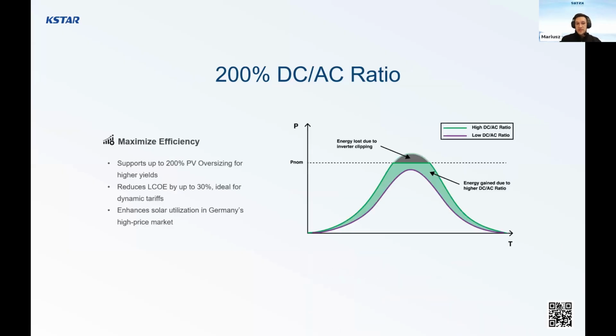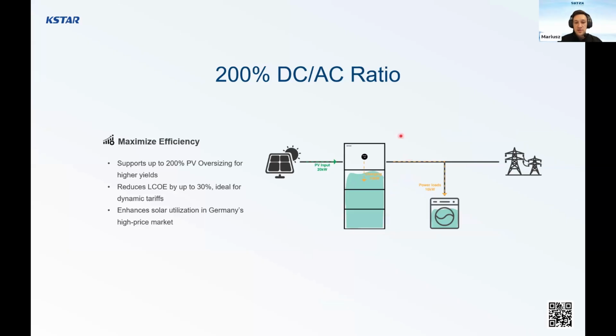Regarding the 200% DC-AC ratio, that's what I mentioned about. We have two converters. So, for example, if we connect to standard PV string inverters or other brand hybrid inverters, the power can be cut at the maximum nominal level of the inverter. In the case of the KSTAR, if we are considering the high maximum power, we can charge the battery from the excess of the energy, and the rest we can supply to the loads or send to the grid operator.